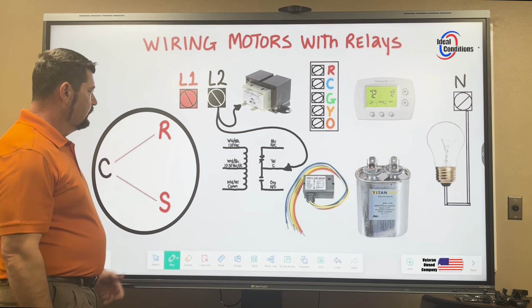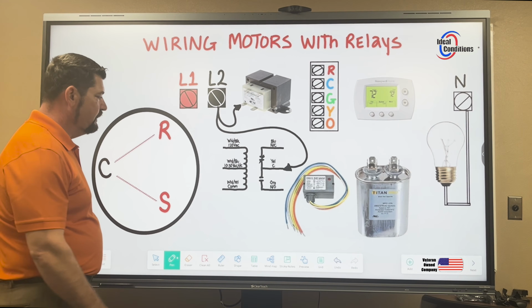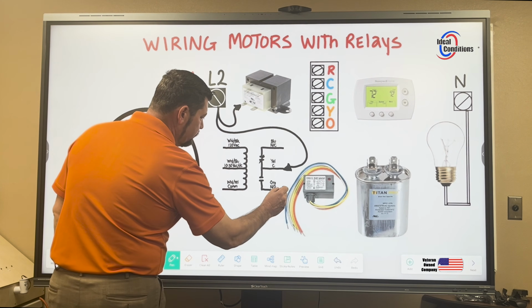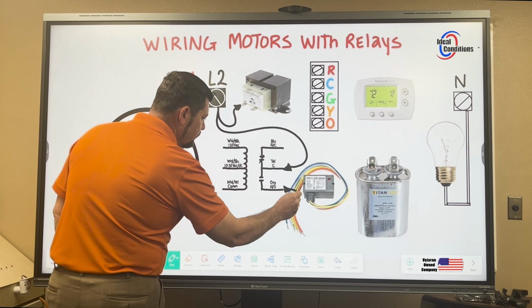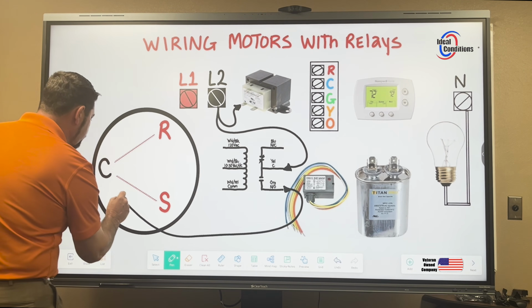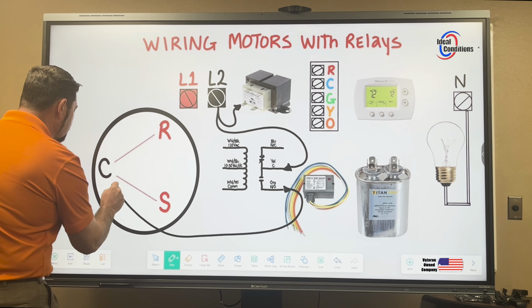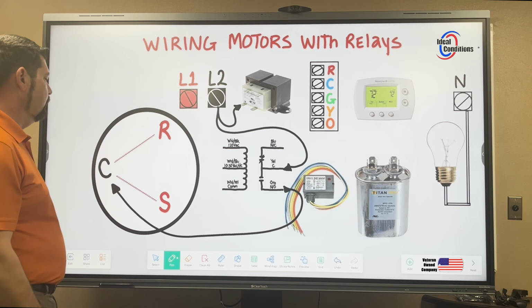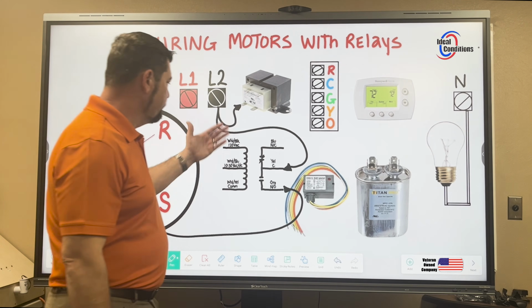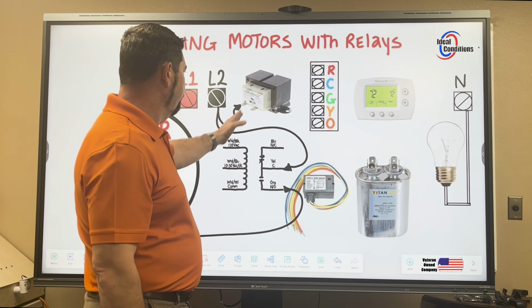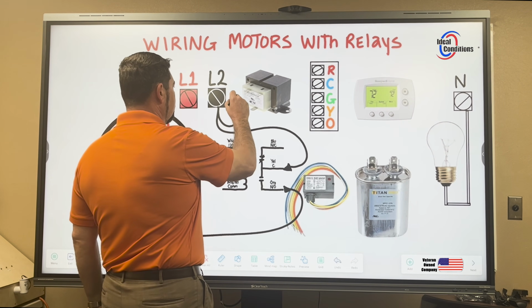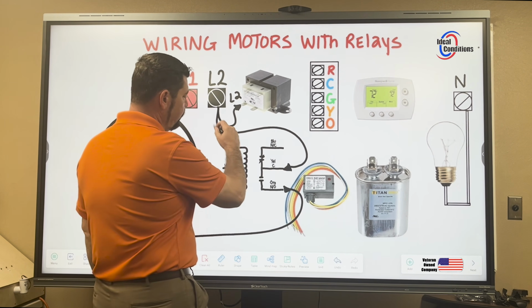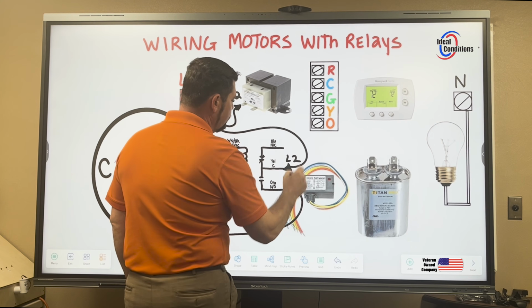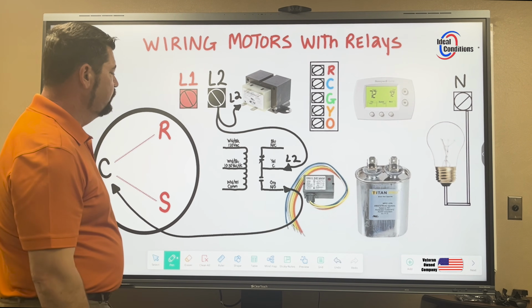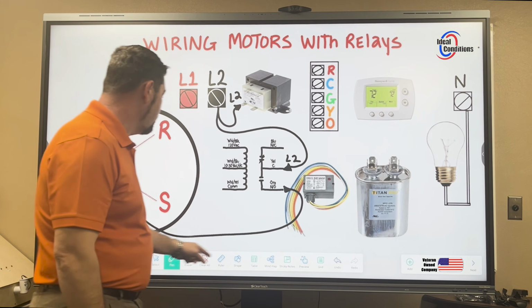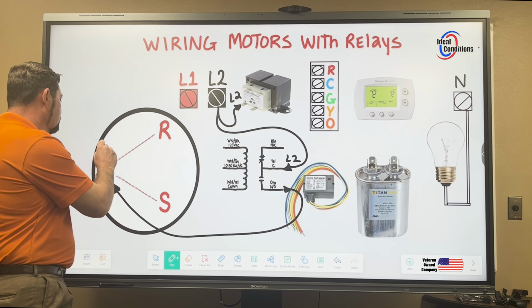And so we're not done yet because I need to come out of my output for normally open, and I'm going to run that over here to common. And there we go. And so now I'm going to step back. I'm going to go ahead and inspect it. L2 to the transformer. Check. L2 to common on the relay. Check. L2 will come out, come over to my motor.